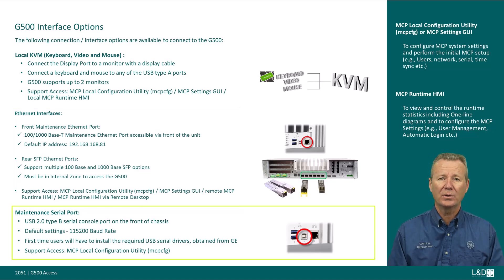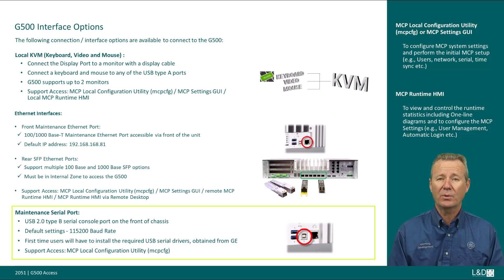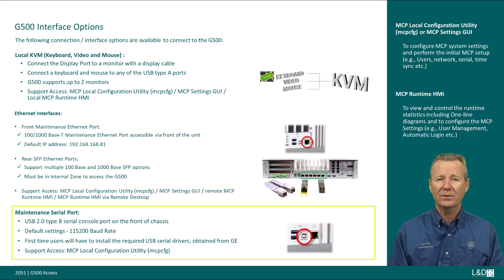The maintenance serial port allows the user to connect to the device via a USB serial cable. It is a USB 2.0 type B serial console port on the front of the chassis. Default settings are 115,200 baud rate. First-time users will have to install the required USB serial drivers. More details can be found in slide 14. We'll also cover support access via the MCP local configuration utility.